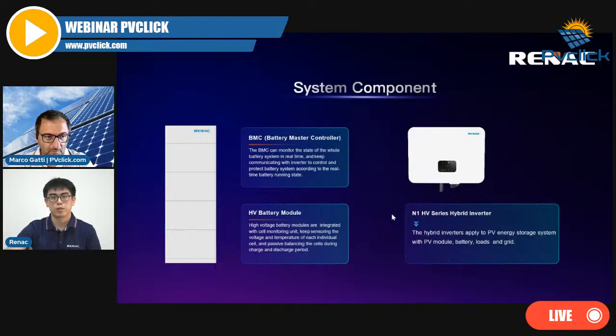This battery system is made up of one BMC, the battery master controller, and several battery modules. The BMC can monitor the state of the whole battery system in real time and keep communicating with the inverter to control and protect the battery system according to the real-time battery running state.